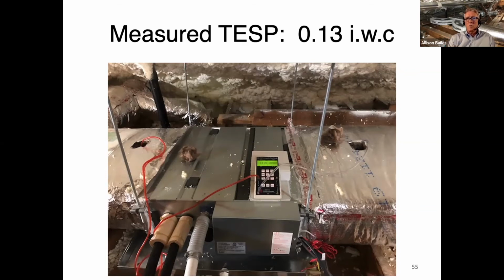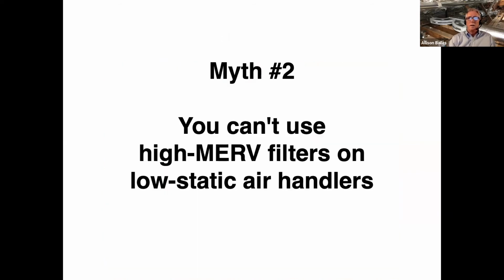And what I haven't told you yet is that I'm not running with the thin little filters that Mitsubishi sends you. I throw those away with the ducted systems. And I use real MERV 13 high efficiency filters, which gets us to myth number 2. You can't use high MERV filters on low static air handlers. Well, some HVAC people think you can't use high MERV filters on anything.